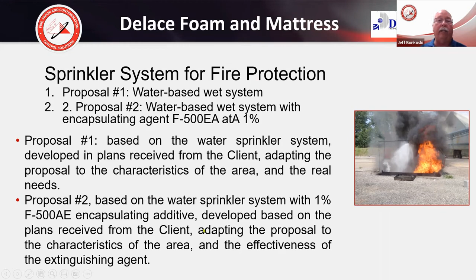And when they did the test, they looked at the water. They used 1,000 liters of water. They used 100% of the water, and they were not able to extinguish the fire. Right here, with 1% of F500 in the water, again, same 1,000 liters, but let's look at the density. Here, 0.4; at 1%, 0.2. Let's look at the pump pressure: 40 PSI down to 10 PSI.